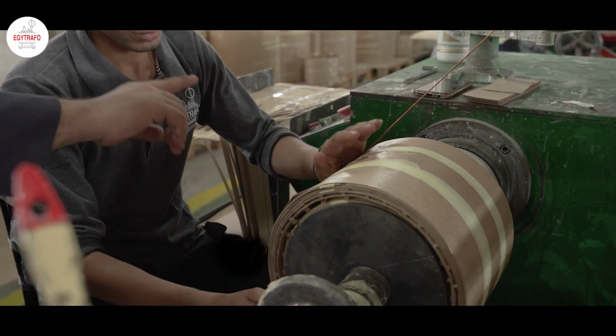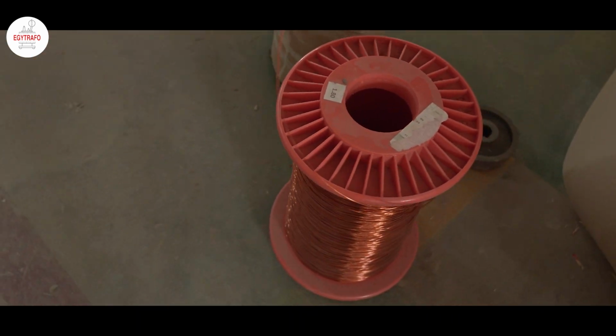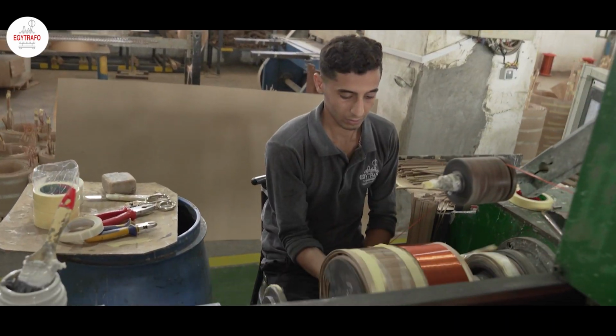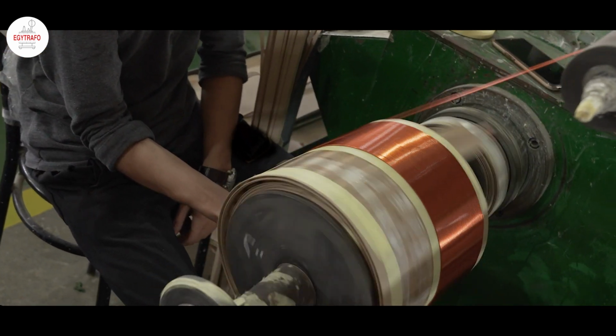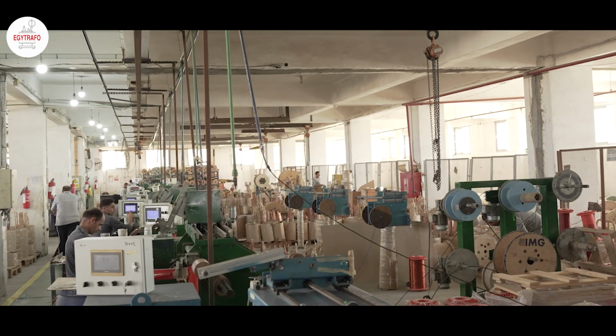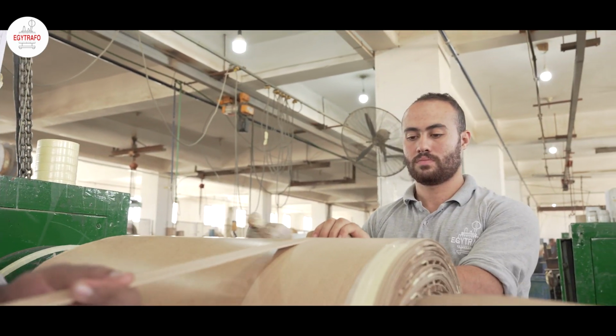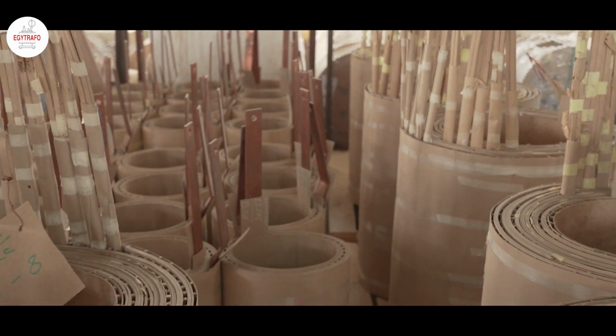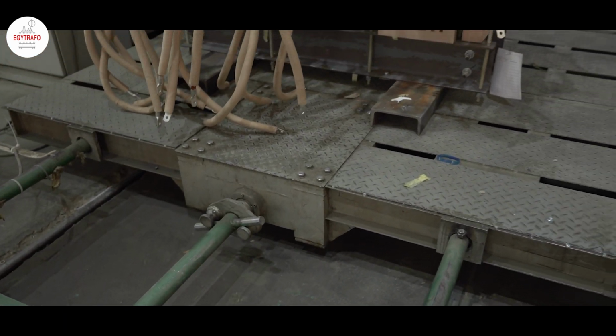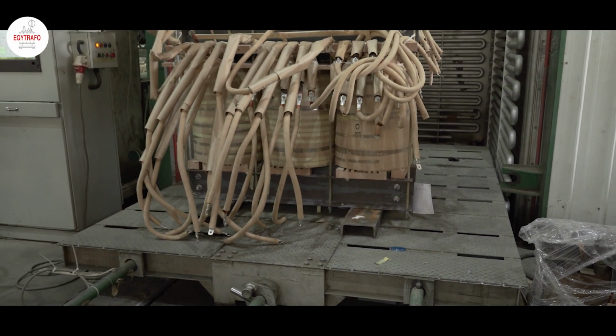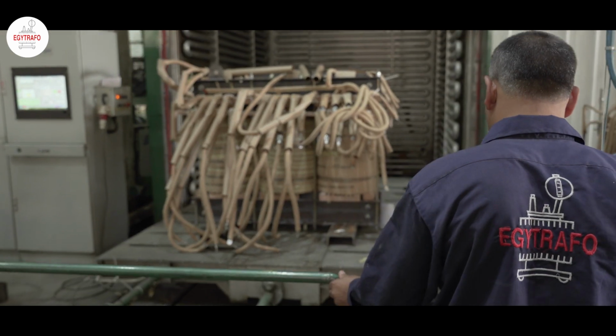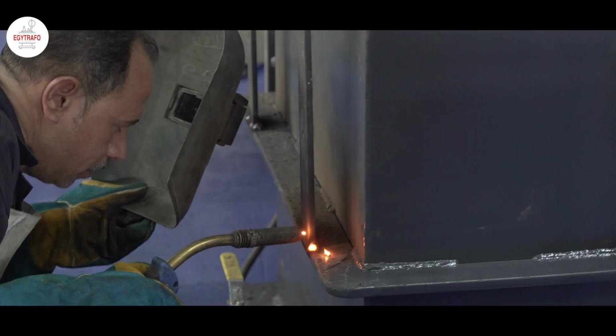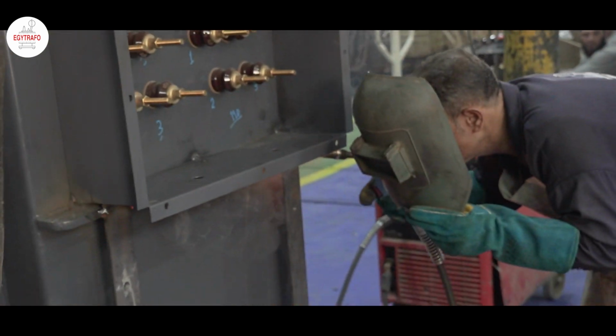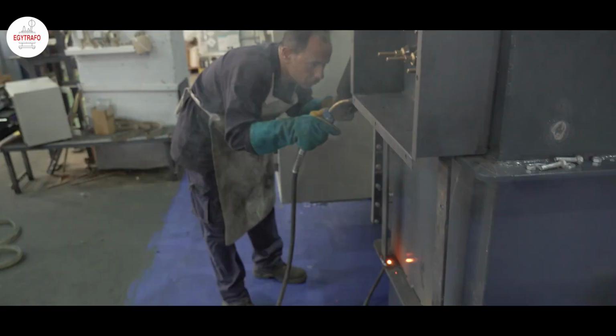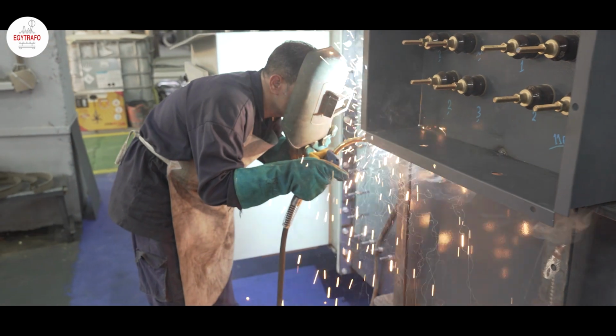They are insulated with pure cellulose or double enamel. The high-voltage windings are wound either with round, double enamel insulated or rectangular paper insulated wire. The low-voltage windings are wound with rectangular paper insulated wire, enamel wire or foil. Tank walls are made of corrugated cooling surfaces. The bottom plate, side and frames are of welded construction. The welds are tested for oil tightness.